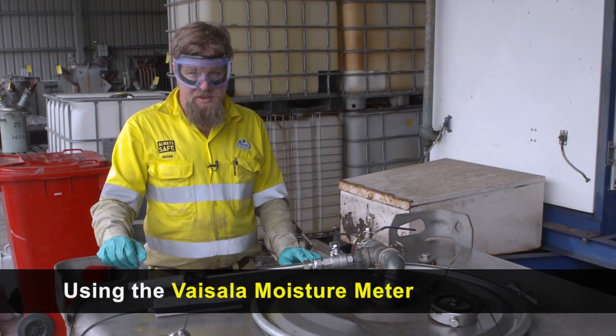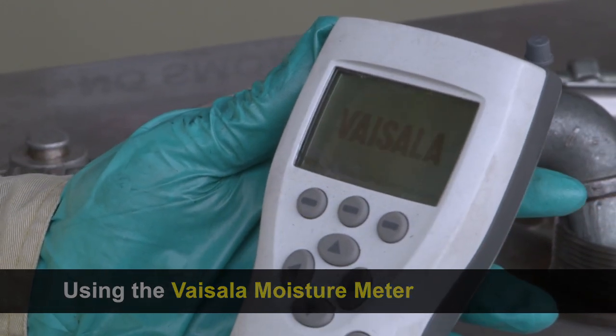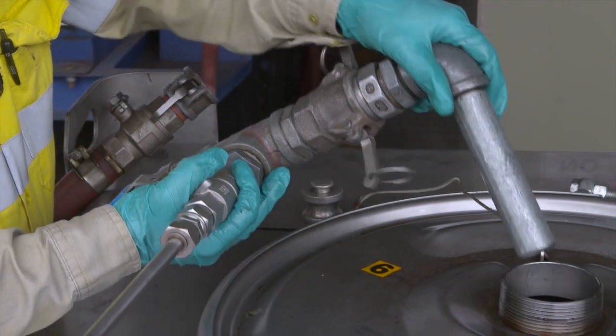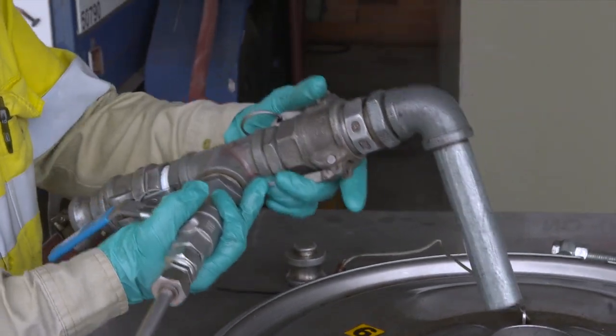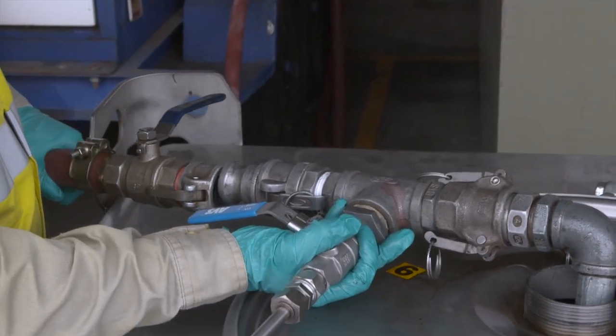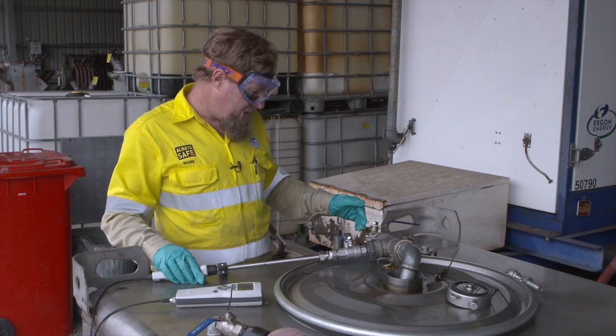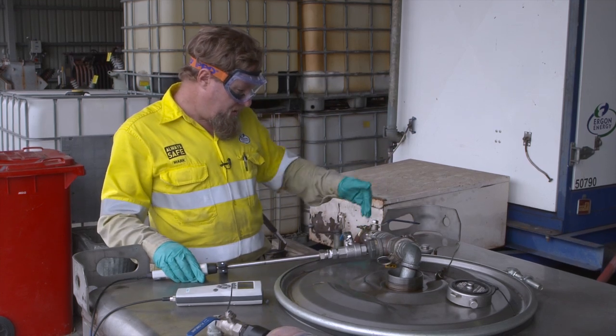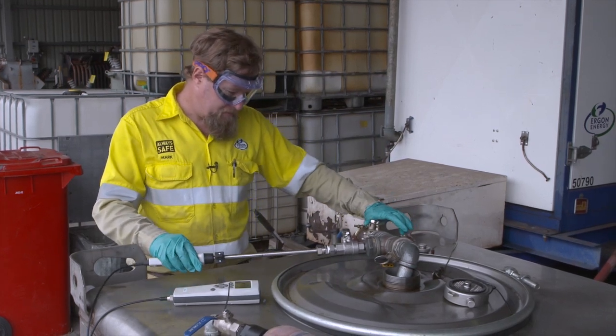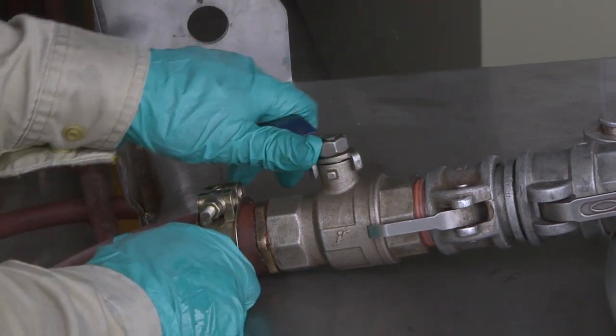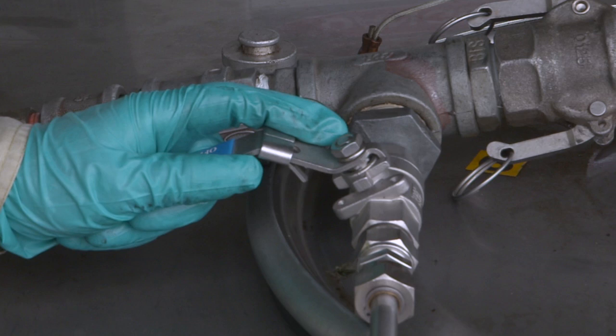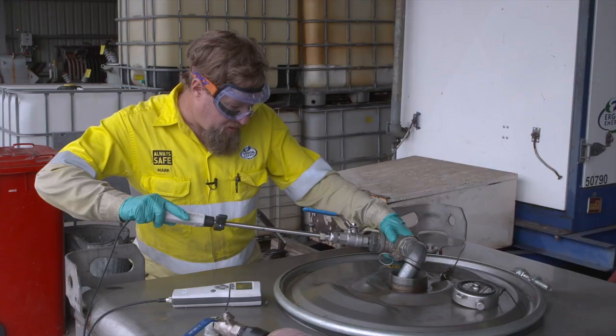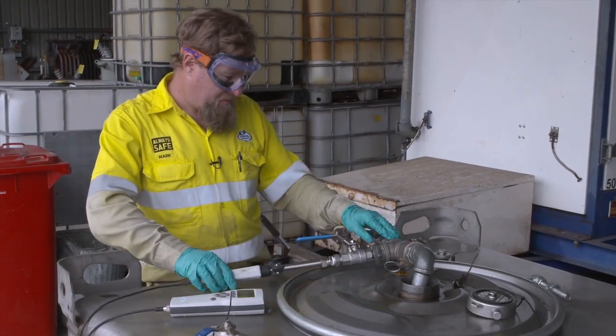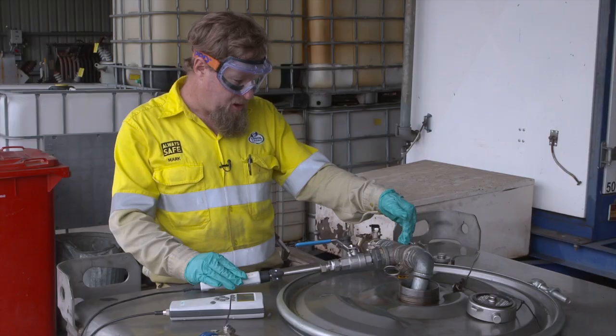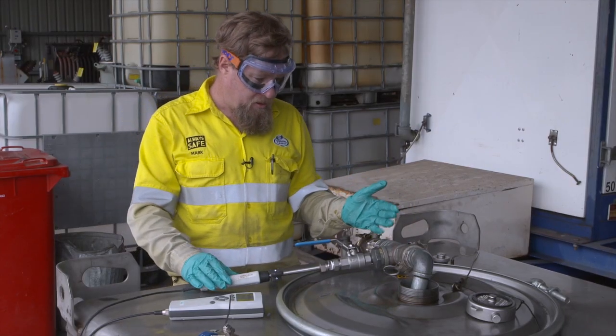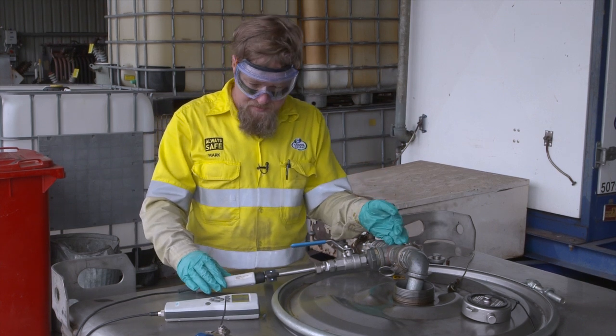When testing the moisture using the Vaisala moisture meter, this is how to do it. We've got our manifold fitted with cam locks, so therefore it can be taken away and used somewhere else. For this instance, I've got it set in line with a feed line coming in with the tap, which I then will open. Then open the probe tap and insert the probe into the end. The probe that we're using has a sensor right at the end, which requires a flow of oil past it to get a correct reading.